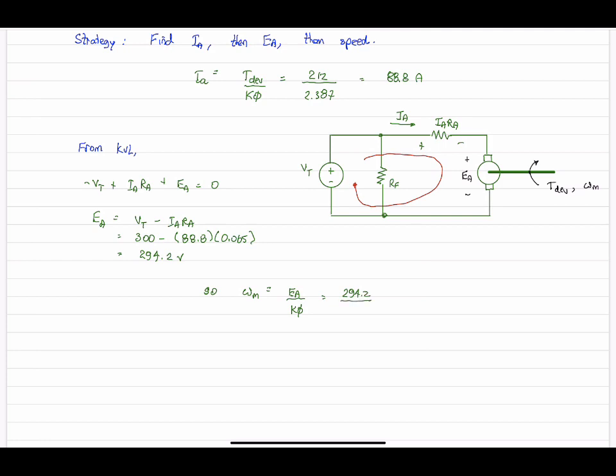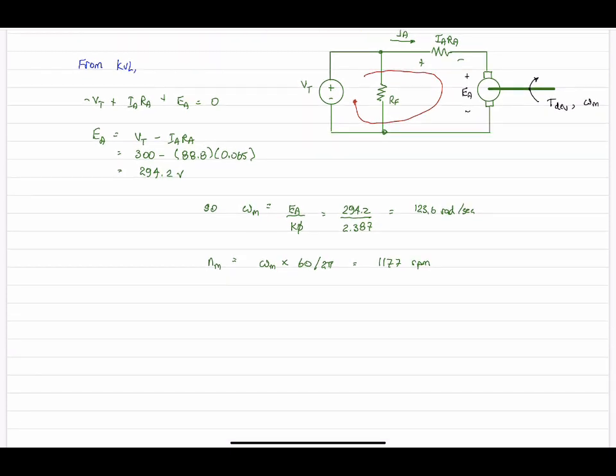So then our motor speed, from the other machine equation, is simply induced voltage divided by the machine constant, 123.6 radians per second. Quick conversion, that is 1177 RPM revolutions per minute.